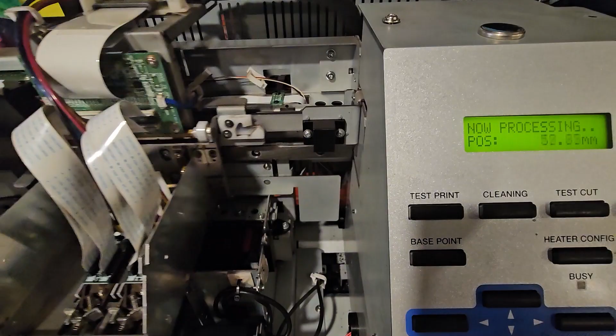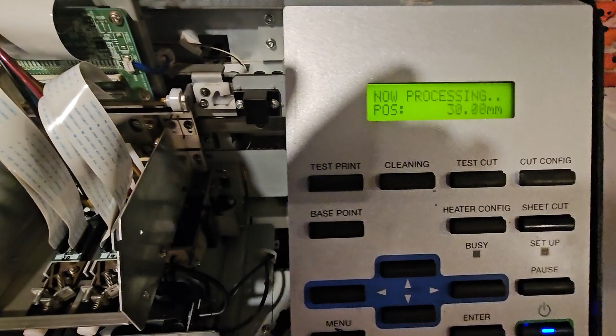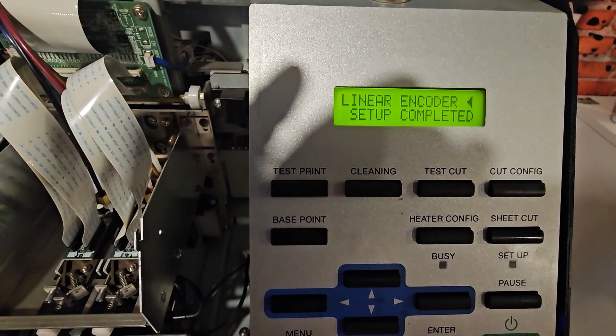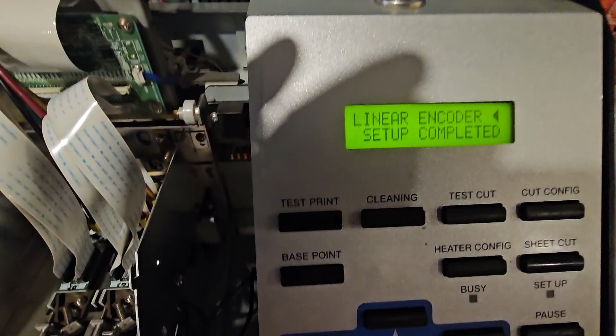All right, she's gonna go down to the end of the machine. There we go. Now this machine, we just replaced both, so I know it's good. So here we go. You can see it says linear encoder setup completed. Now if this fails, then you likely have a problem. If it fails, then you need to replace the encoder strip or the sensor.